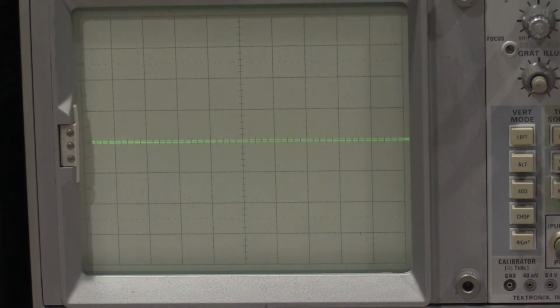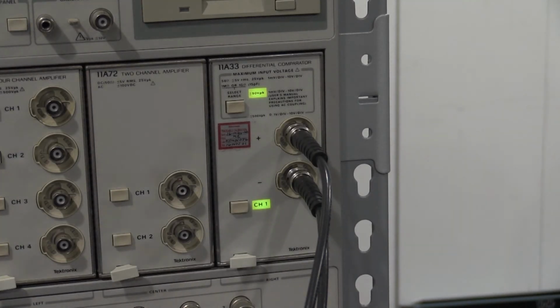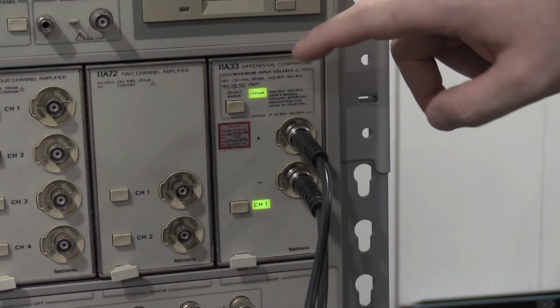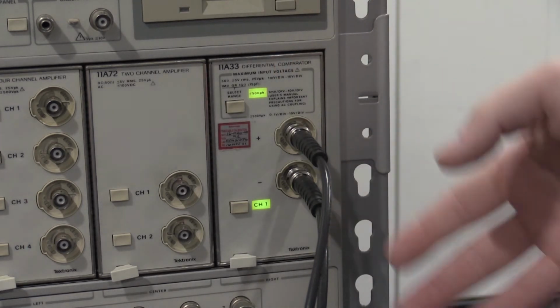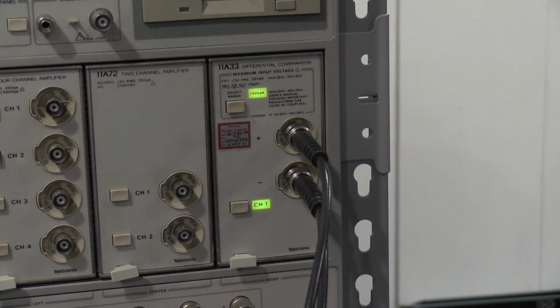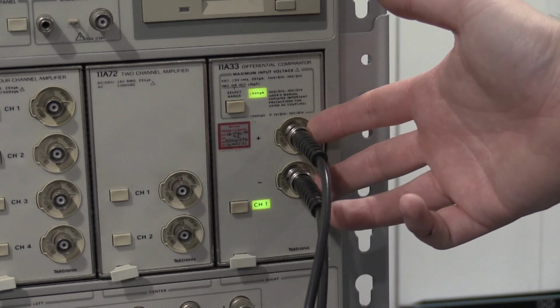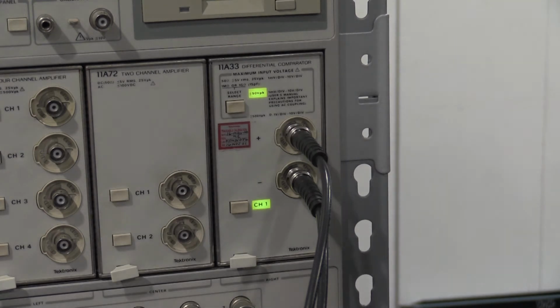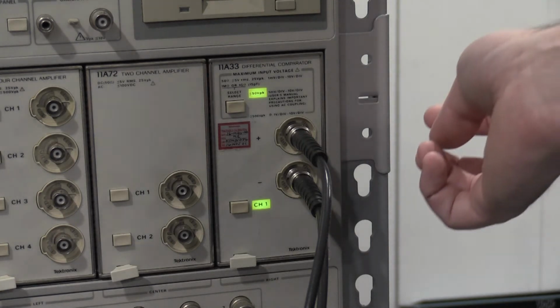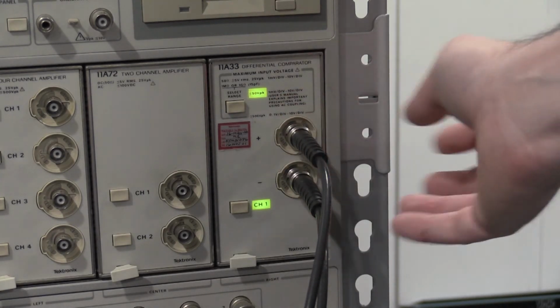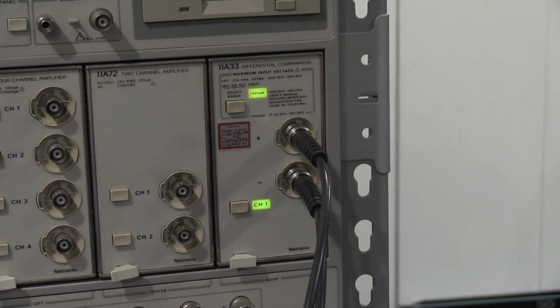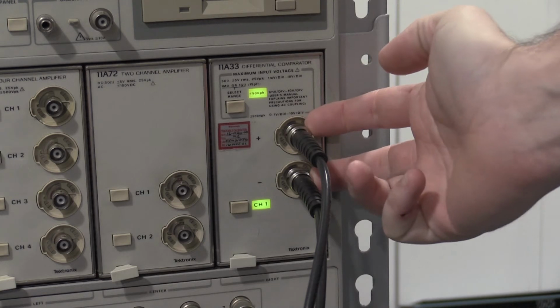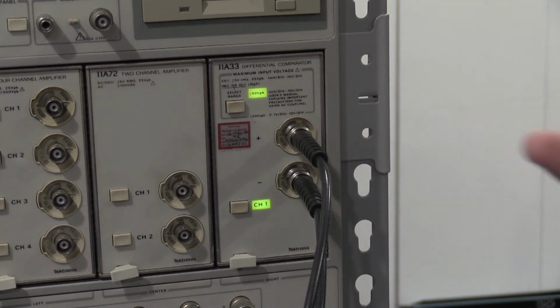It's fine. Okay, deviating slightly from the calibration document because I have available an 11A33 differential comparator. Using the 7A26 in inverting and adding mode to give it differential inputs in a 7603, which is what's called out by the calibration document, gives me about 75 to 90 megahertz of bandwidth. The 11A33 has 150 megahertz of bandwidth, so I'm getting more viewable signal, and it's a true differential comparator as opposed to using the invert, which has some error to it. I have it, so we're going to use it.